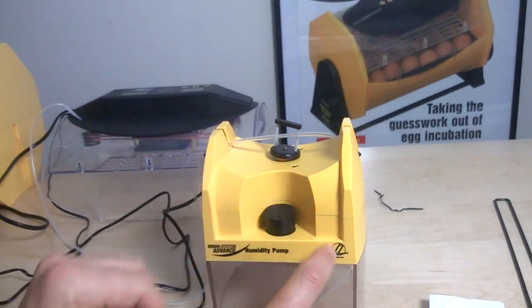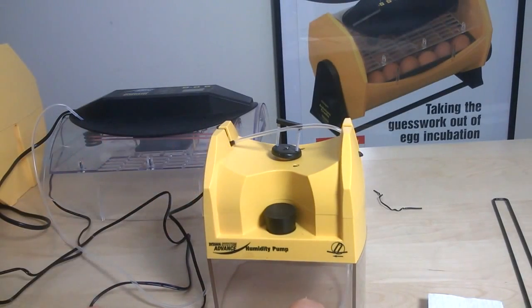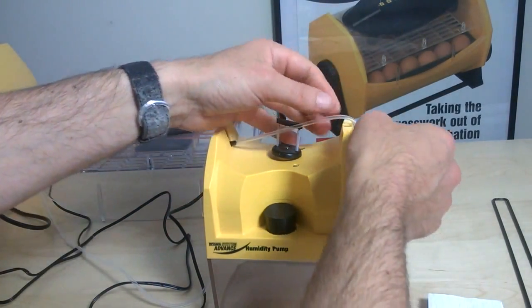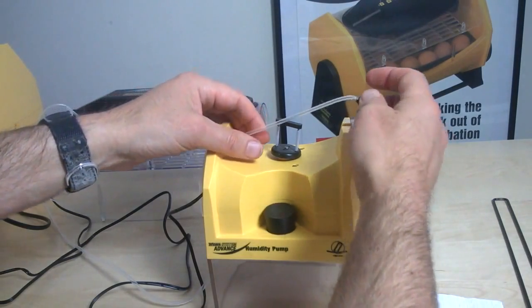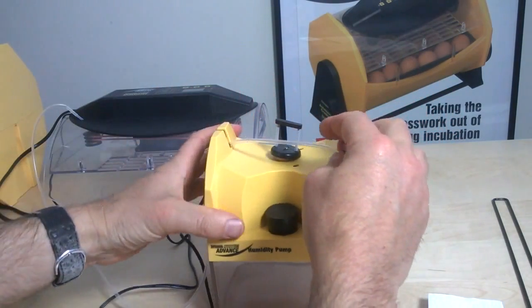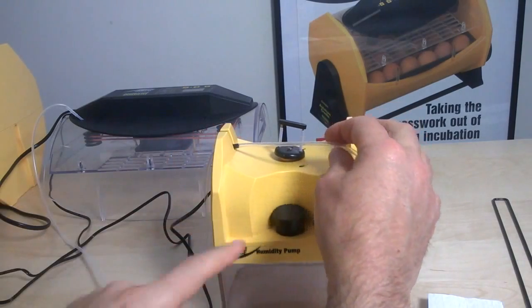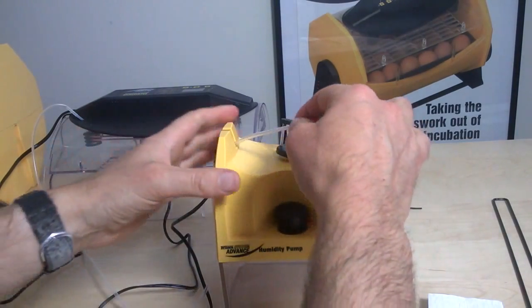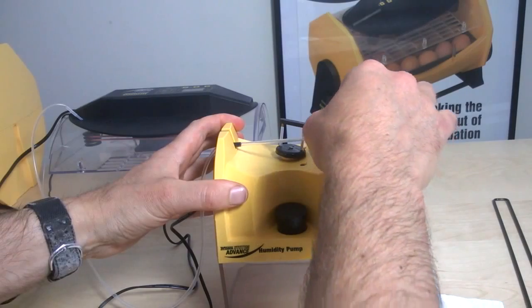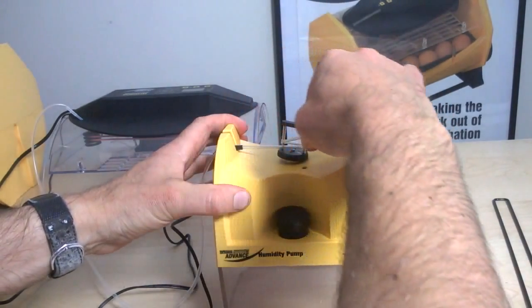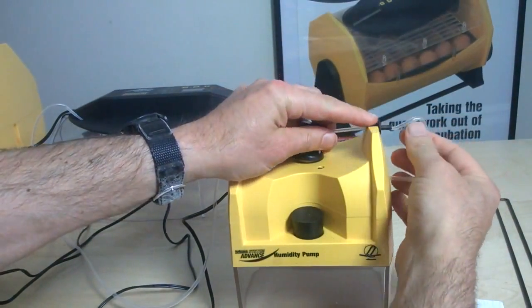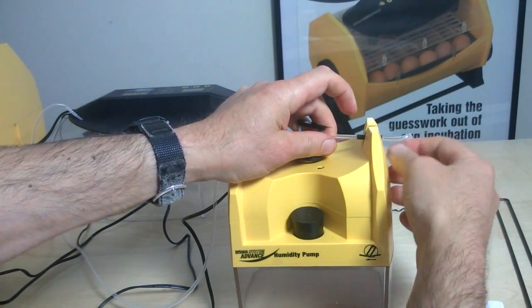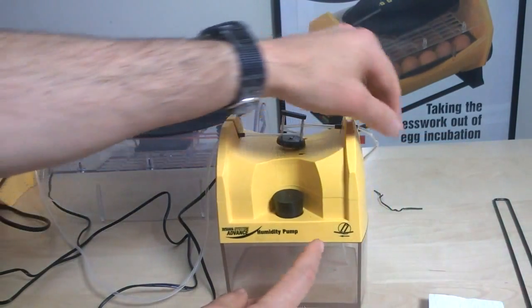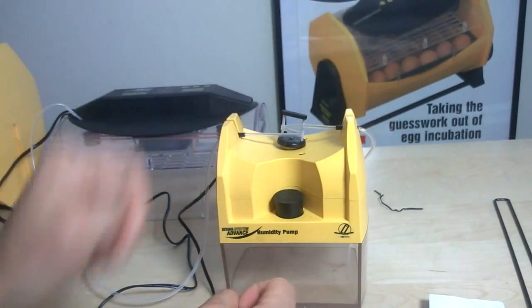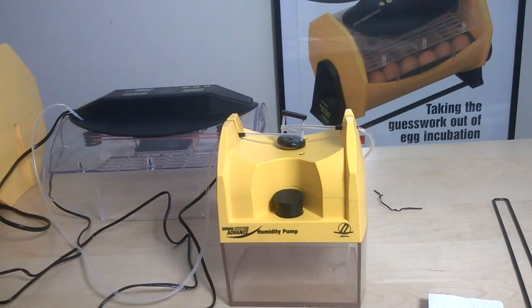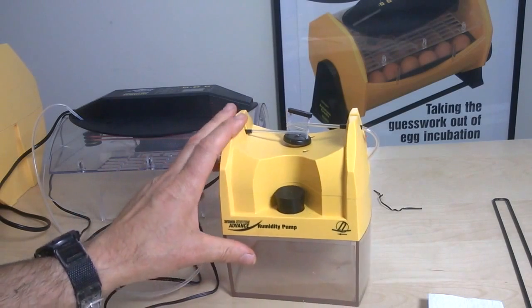Now, the important point at this point is to remember that this tubing here needs to be fitted around the capstan head in a particular way. So going with the bung facing you, going from left to right, you go round in an anti-clockwise direction around the capstan head and down into the reservoir, making sure not to pinch the tubing so that water can pass freely through it. And it's as simple as that.